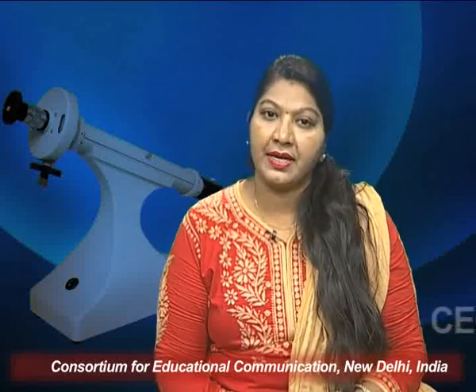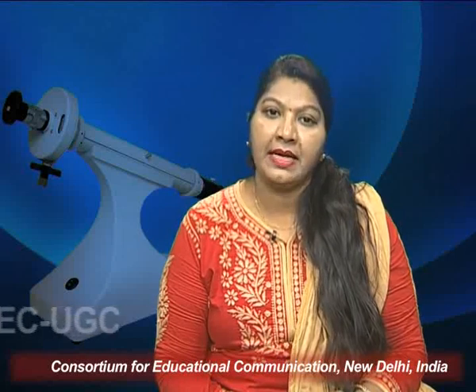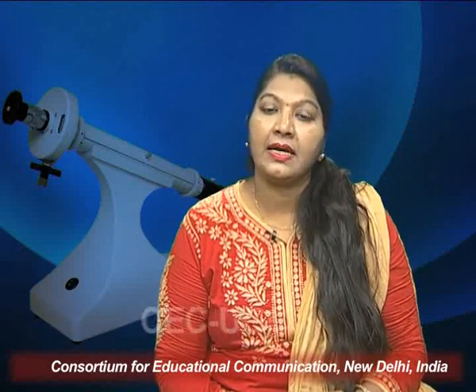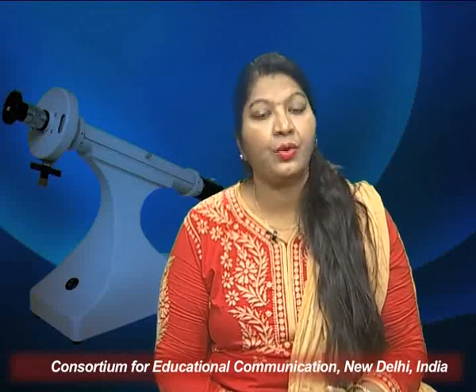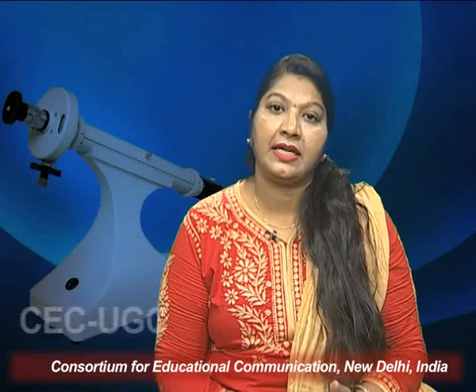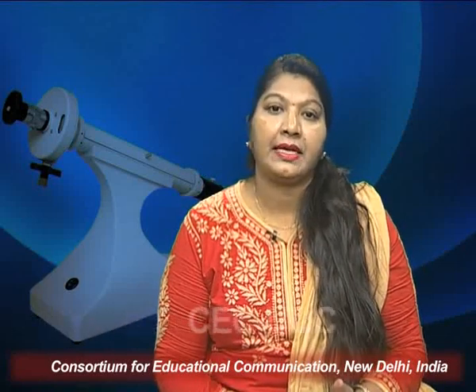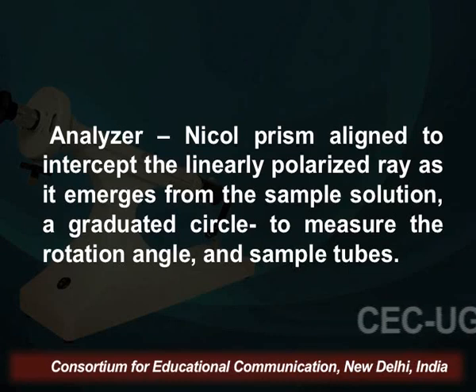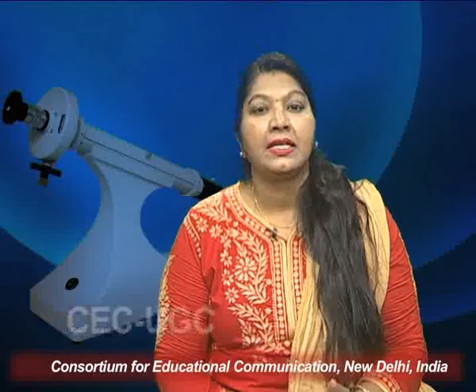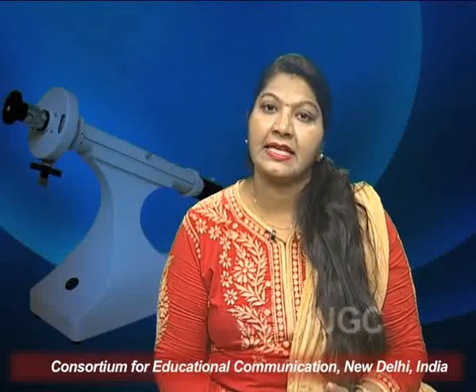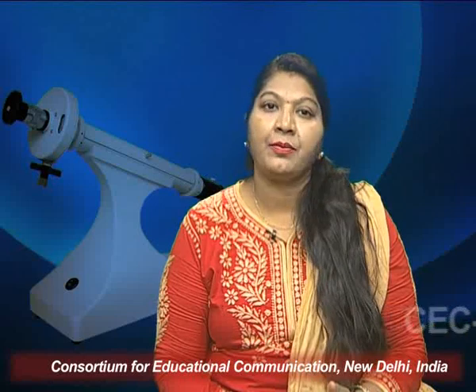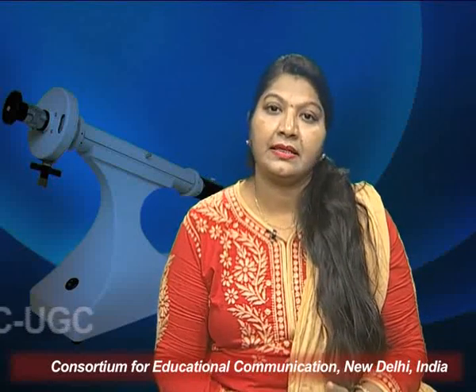Polarimeter consists of a polarized light source, the sodium lamp, a polarizer that is made of quartz prism material, and the analyzer can also be of a similar form. The Nicol prism is aligned to intercept the linearly polarized ray as it emerges from the sample solution. So we use two Nicol prisms, first as a polarizer and second as an analyzer, just to get the specific rotation of an optically active solution.